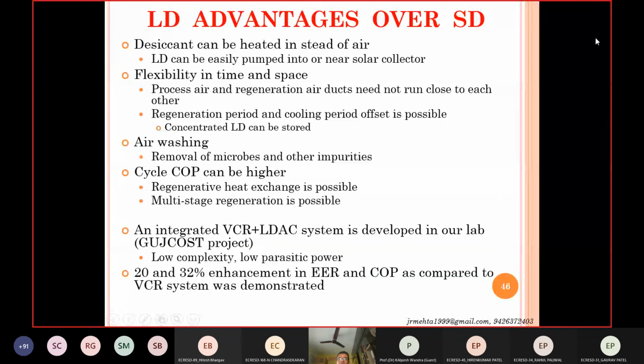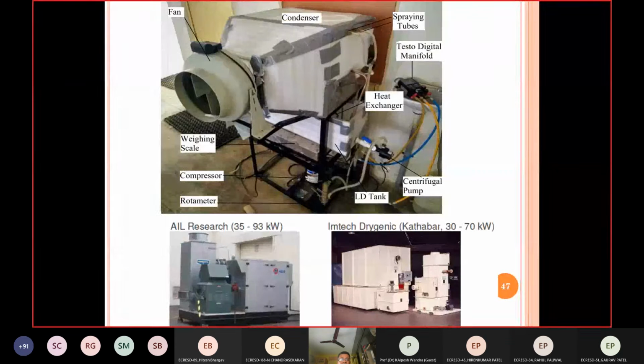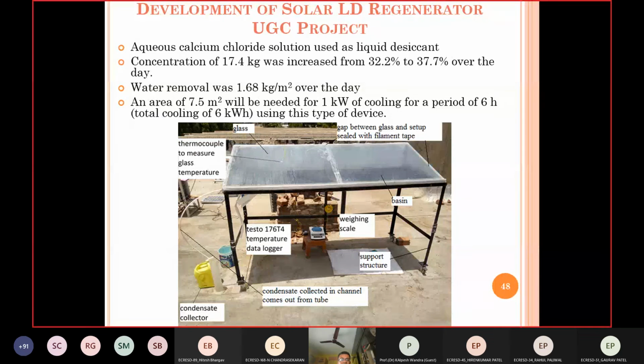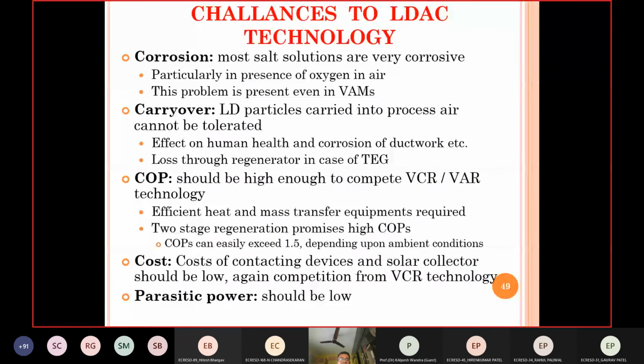Some advantages of a liquid desiccant based system as compared to the solid desiccant are that there is flexibility in time, you can regenerate and store, and you can also easily pump it. So those are some of the possible advantages of liquid desiccant systems as compared to solid desiccant systems, but they are not yet much seen in the market because of certain issues like corrosion, carryover of the liquid desiccant particles into the space, and the COPs. Finally, at least from the primary energy consumption point of view, the COP should be competitive as compared to the vapor compression based system, and the initial cost also should not be prohibitive.